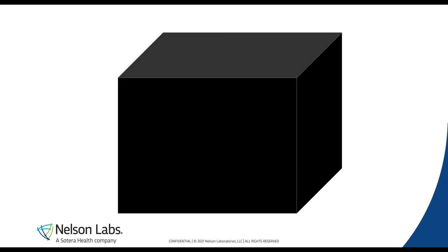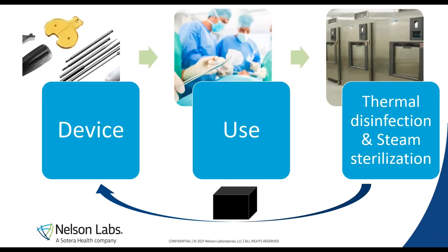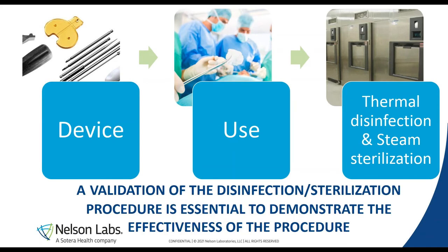Because you have to rely on that process and it's a complete black box, in the healthcare industry it is very important that all these steps are validated. The validation of the disinfection and sterilization procedure is really essential to demonstrate the effectiveness of that procedure and to make sure that you have a safe device.